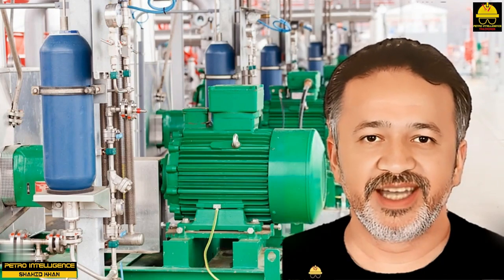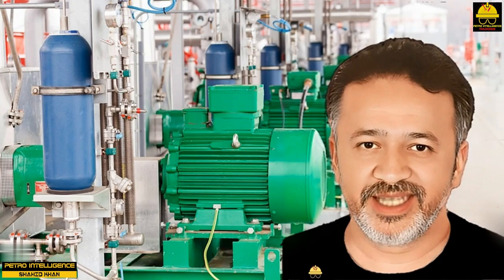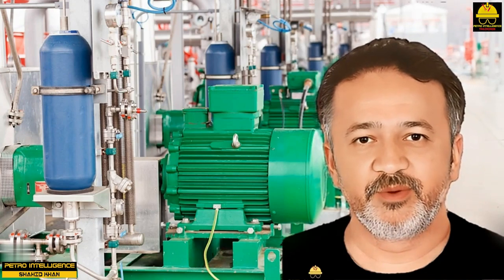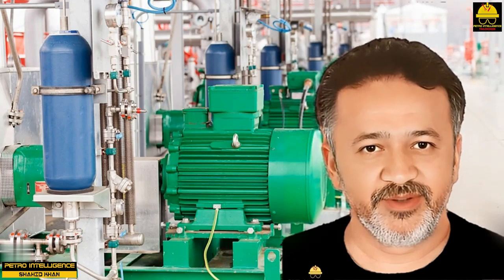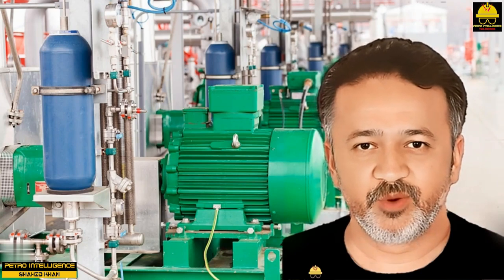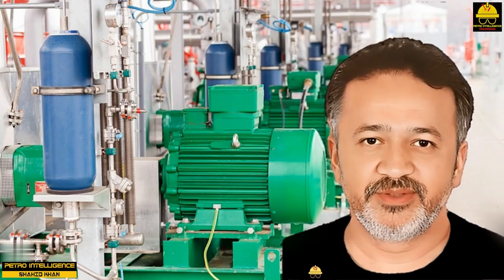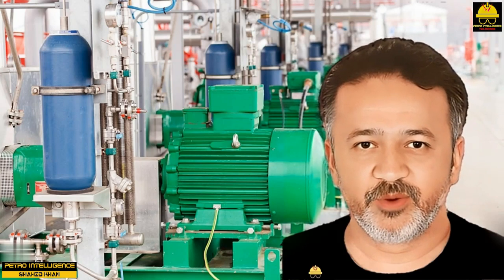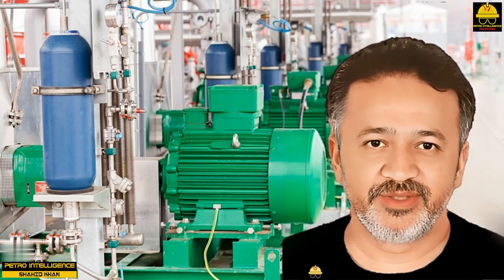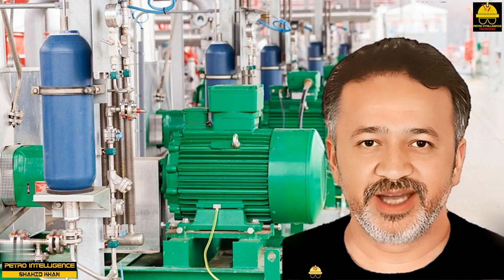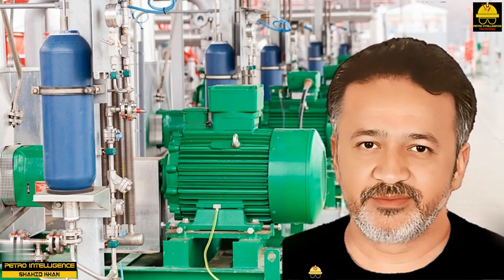Another problem associated with centrifugal pump operation is vapor lock. Vapor lock is a condition in which a pump loses liquid prime, and the impellers rotate in vapor. Bleed valves are located on the pump to remove air from the system. The pump must be shut down and air bled out before it will operate properly.